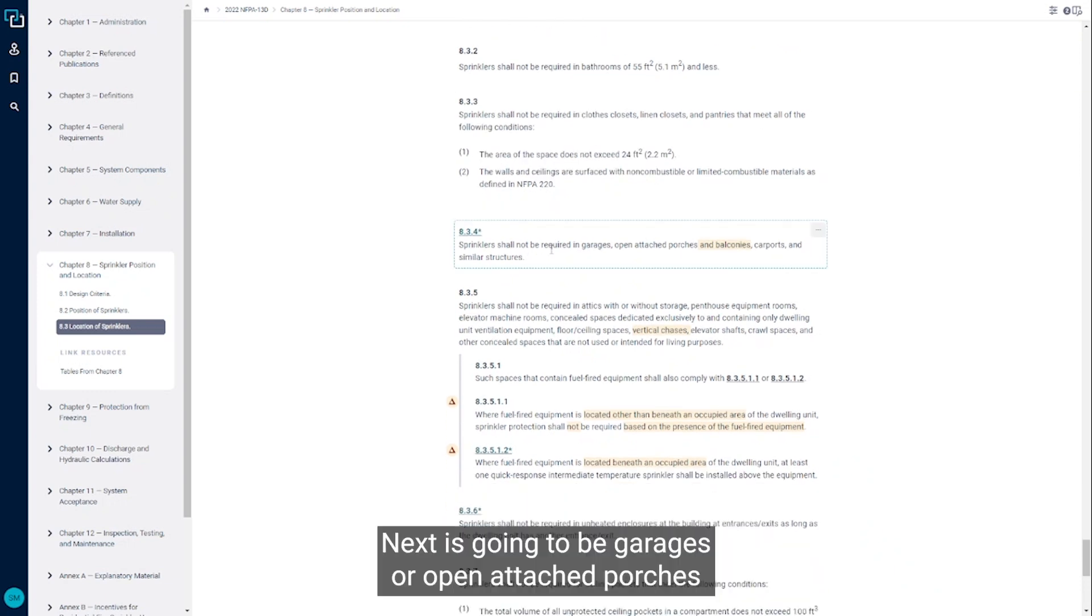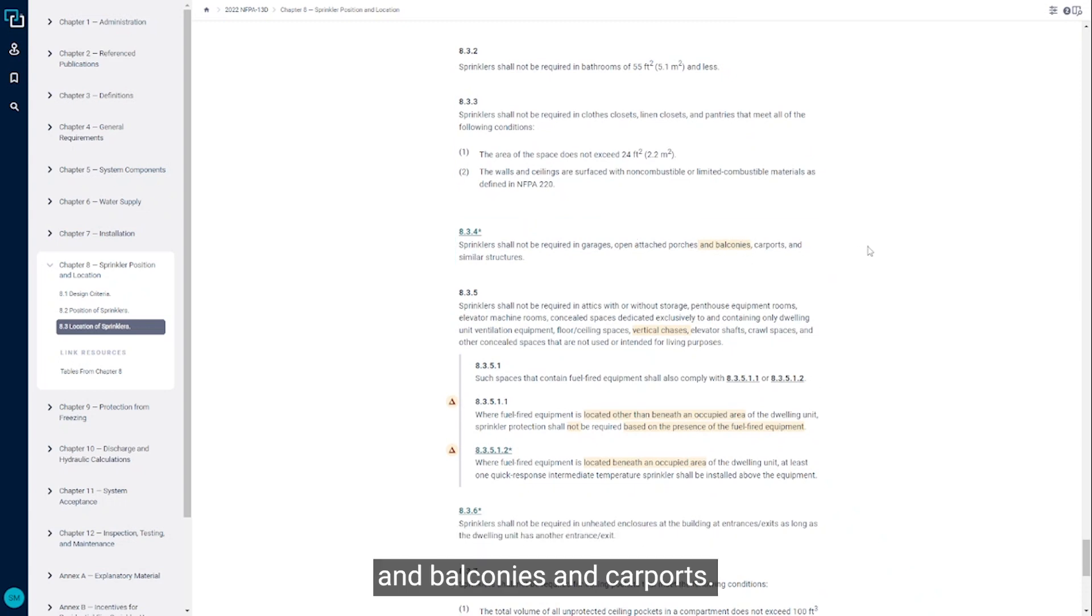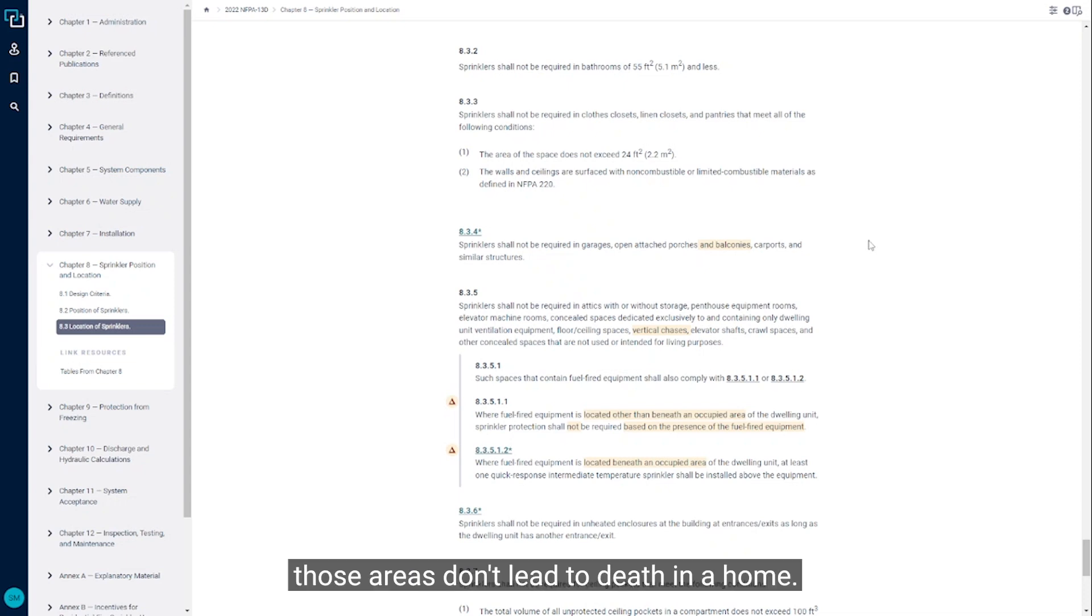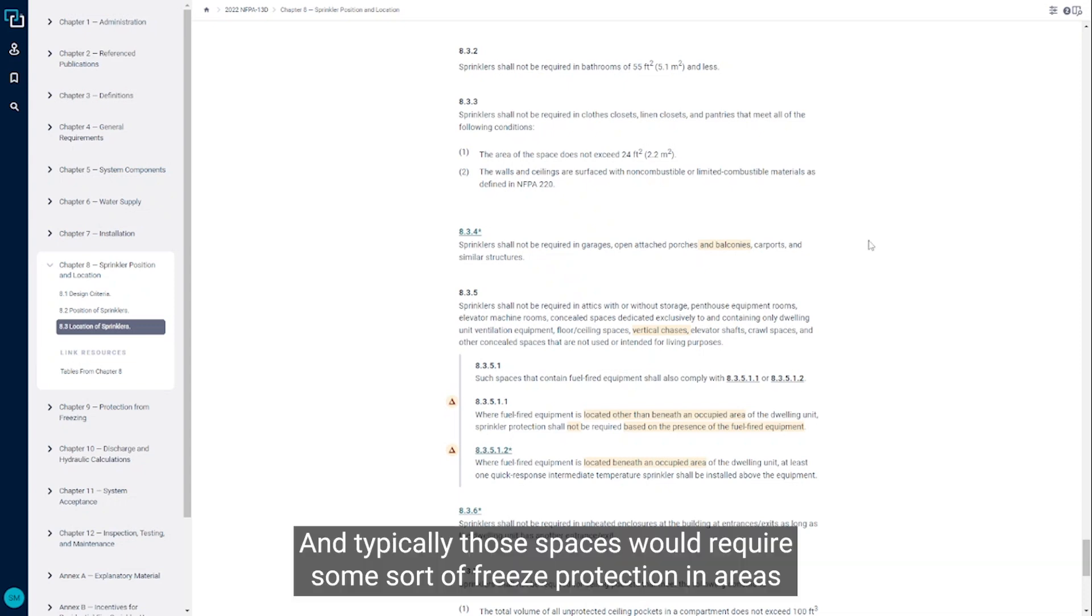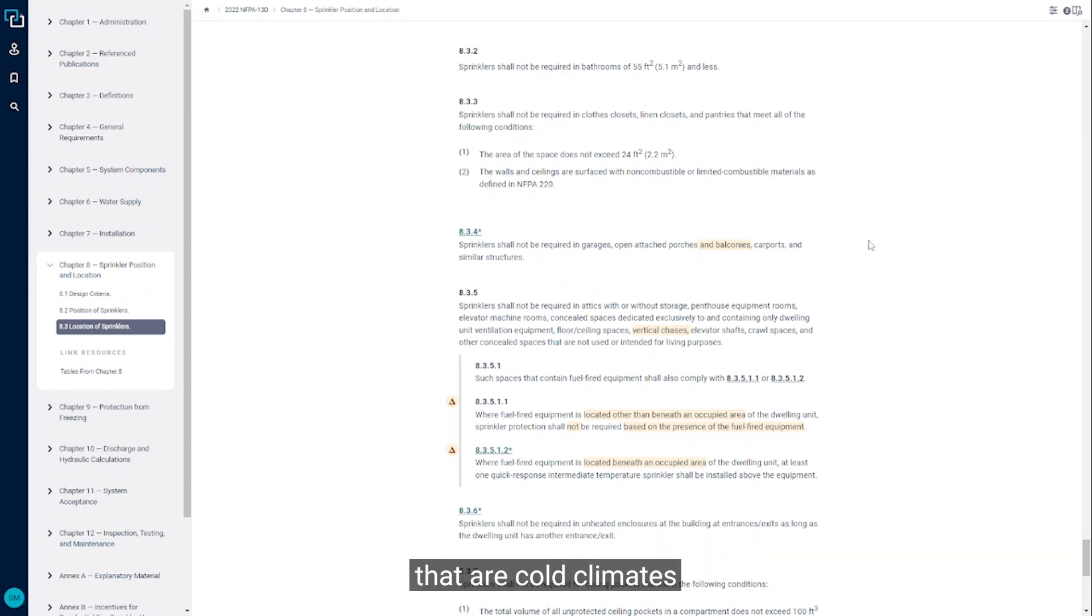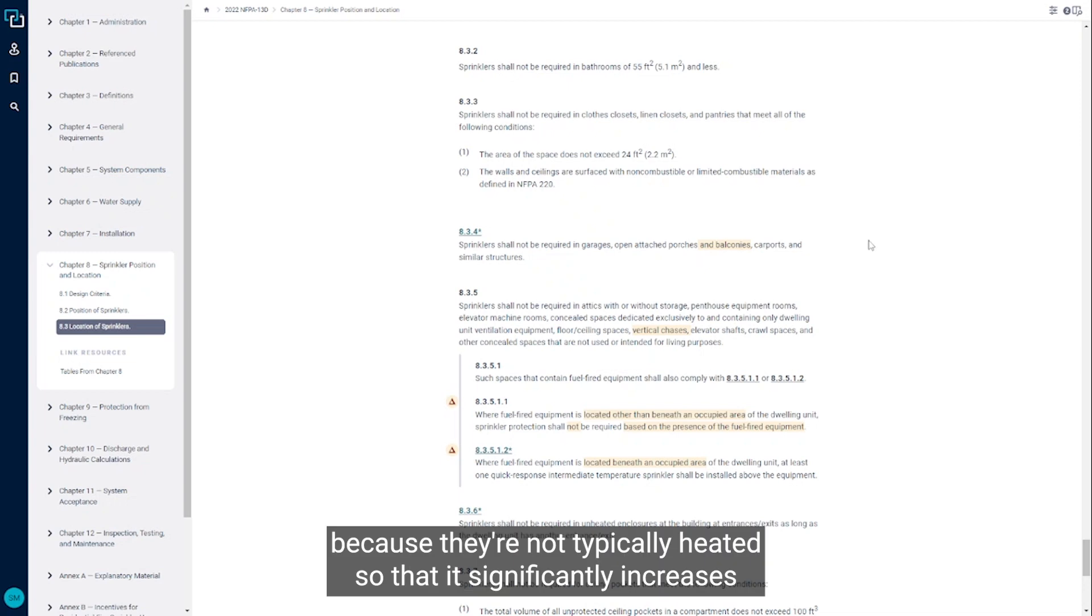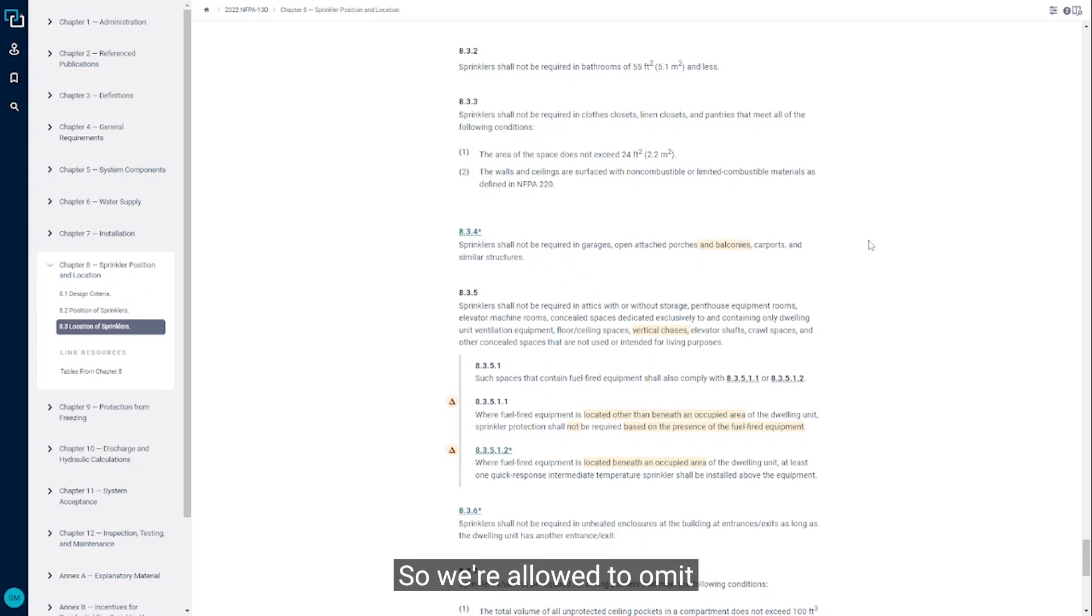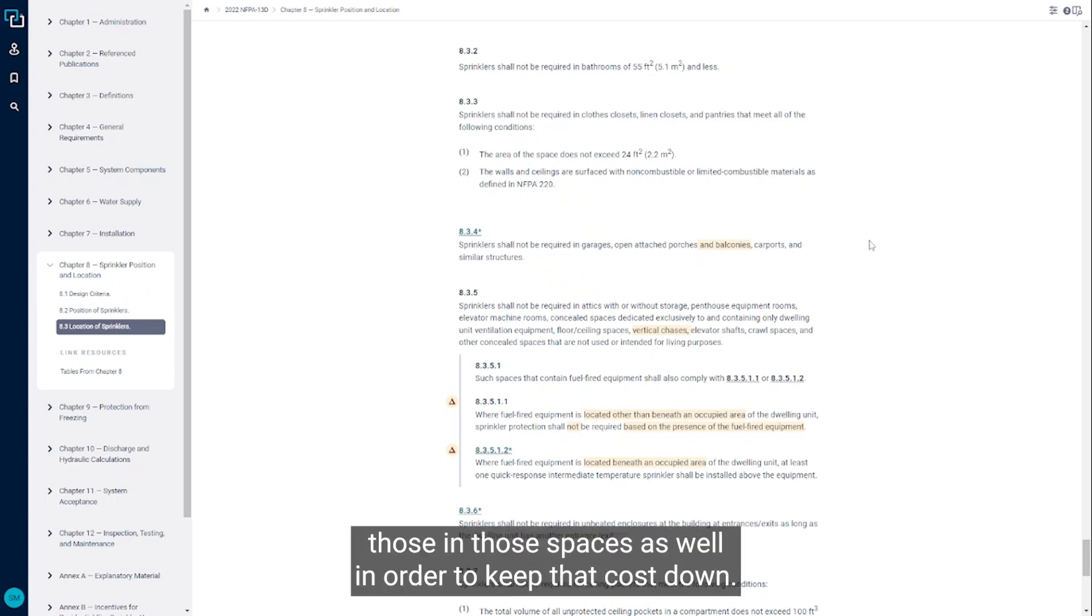Next is going to be garages or open attached porches and balconies and carports. Fires in those areas don't lead to death in a home, and typically those spaces would require some sort of freeze protection in cold climates because they're not typically heated. That significantly increases the cost to install sprinklers in those spaces, so we're allowed to omit those in order to keep that cost down.